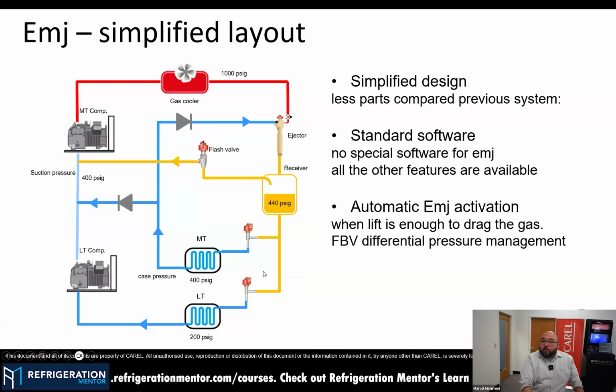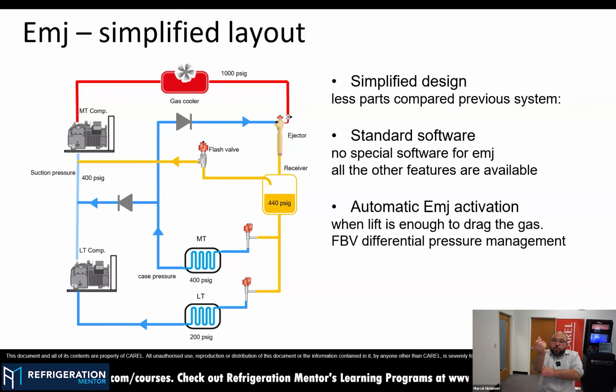Okay, talking about the system, I have my compressor pack and my rack. Where should I install the ejector? How should I pipe it? Basically, here I put a diagram of how the ejector will be installed when you see it in the field. We have our MT compressor line going to the gas cooler. I put just the main components; there are many others like filters and the oil separator. Then from the gas cooler, the pipe comes into the ejector here.